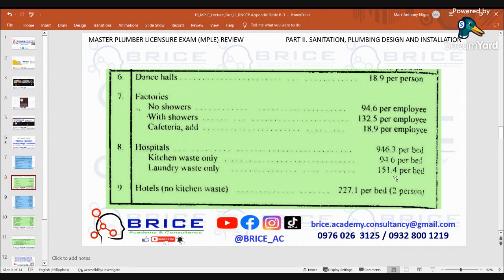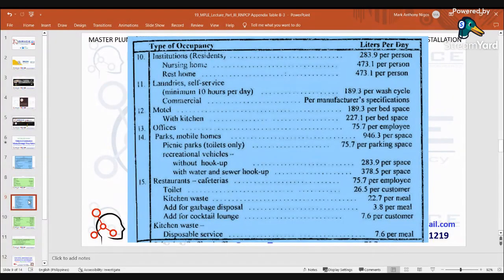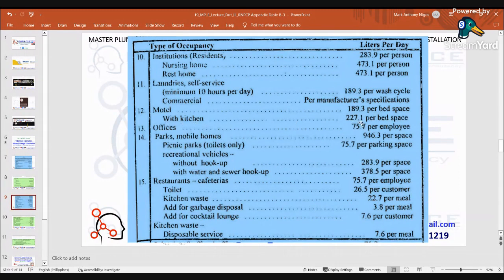With cafeteria, add 18.9 liters per employee. Number 8: Hospitals — 946.3 liters per bed; kitchen waste only: 94.6 liters per bed; laundry waste only: 151.4 liters per bed. Number 9: Hotels, no kitchen waste: 227.1 liters per bed or two persons. Number 10: Institutions — residents: 283.9 liters per person. Nursing home — 473.1 liters per person; rest home — 473.1 liters per person. Number 11: Laundries — self-service minimum 10 hours per day: 189.3 liters per wash cycle; commercial per manufacturer specifications. Number 12: Motel — 189.3 liters per bed space; with kitchen: 227.1 liters per bed space.